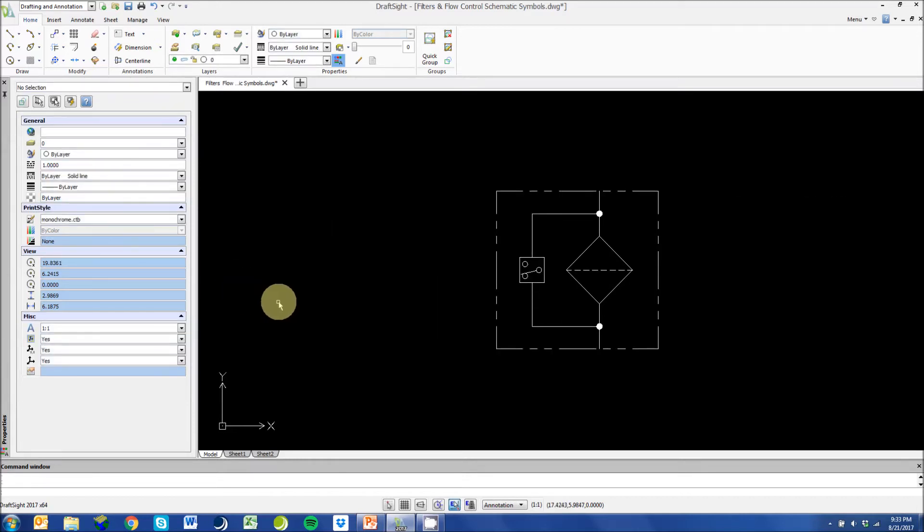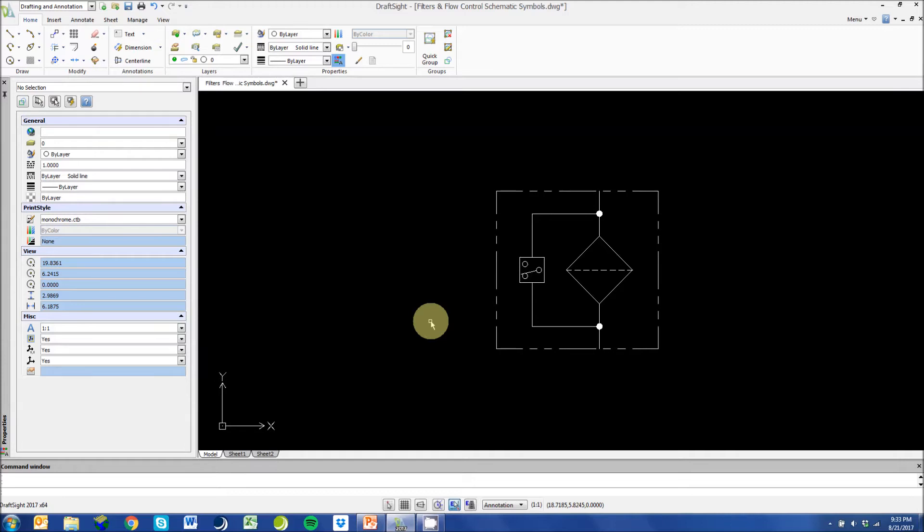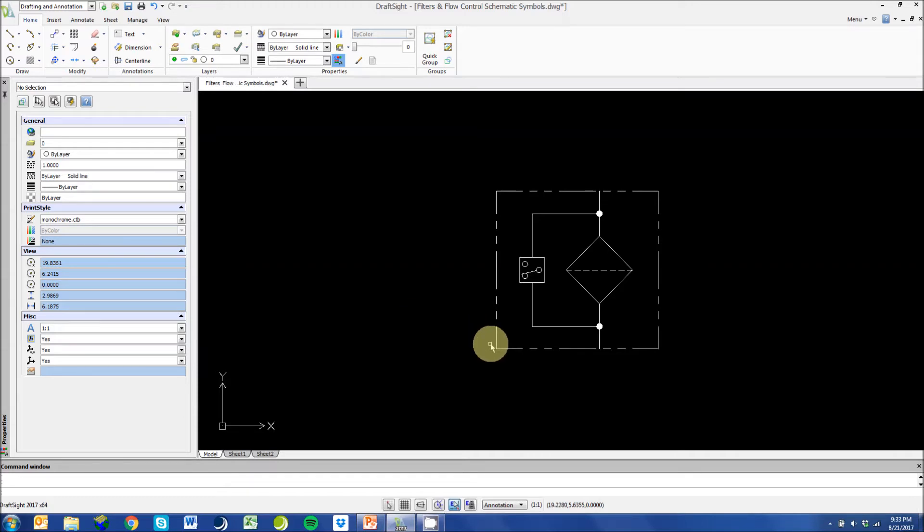This symbol represents a filter with a differential pressure switch. This symbol is used to send signals to PLC or DCS systems to indicate when it is time to change a filter element. Most of our customers will refer to this as a filter alarm.